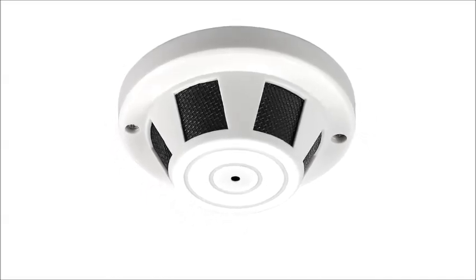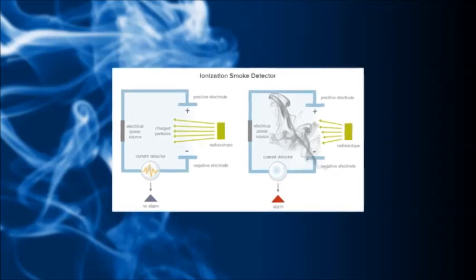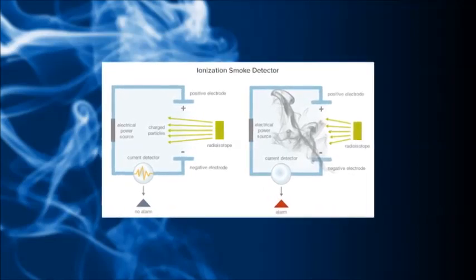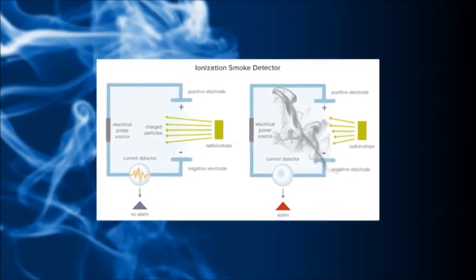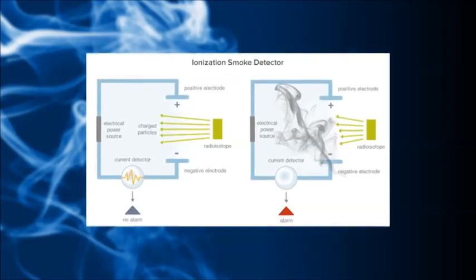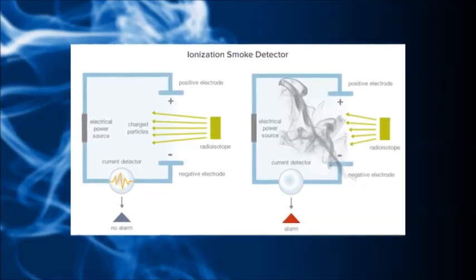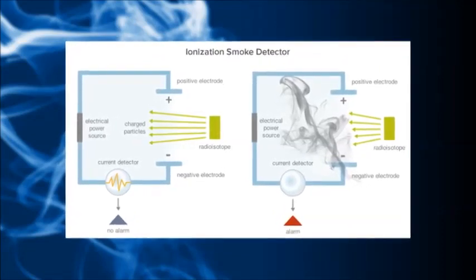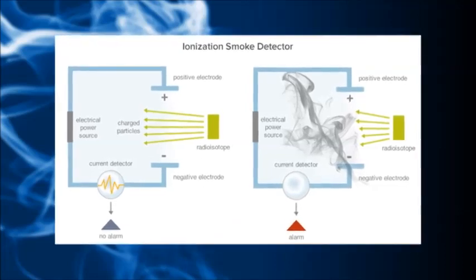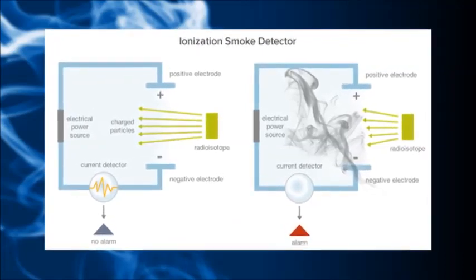When smoke enters the chamber, the particles attach themselves to the charged ions and restore them back to a neutral electrical state. This disrupts the electric current and an alarm is triggered. Hot air can also change the rate at which ionization occurs within the chamber, and this will also trigger the alarm.